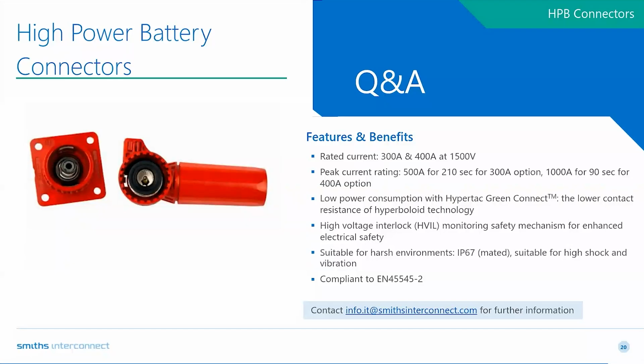We have time for one or two more questions. For a customer choosing between a 300A and 400A version, what are the key selection criteria? The choice between the 300 amp and 400 amp version is mainly based on the nominal current required by the application, and as a result on the cable cross-section that needs to be used. More specifically, the 300 amp version is suitable for cables in the range of 50 to 70 square millimeter, while the 400 amp version is intended for larger cables, typically from 95 to 120 square millimeter.